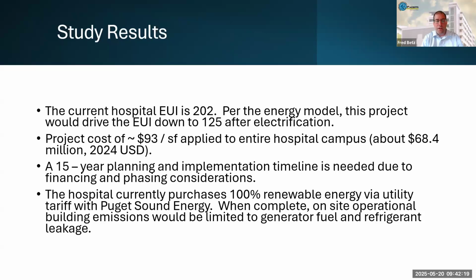One thing I didn't actually mention, which I would do in nearly every other hospital, but was not necessary here, is the airside systems. They're already down to code minimums for air change rates. The patient tower is a dedicated outside air system, providing 2 air changes of 100% outside air, plus zone level or patient room level fan coil units. And I mentioned that those were getting motor upgrades, which had a pretty significant reduction in peak power.